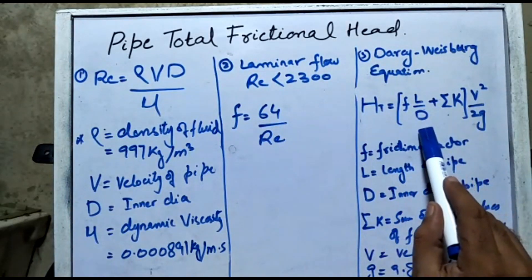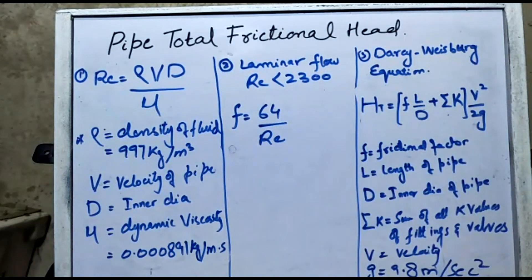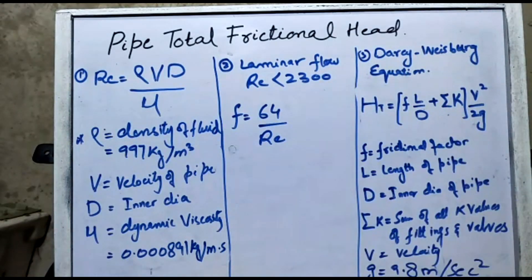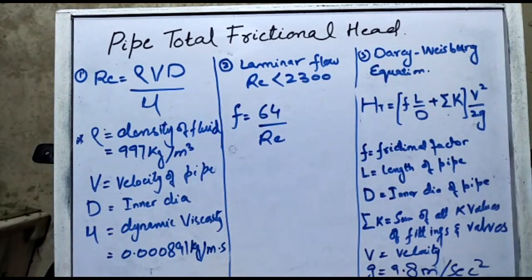...plus the sum of all K-values, multiplied by v²/2g. K-values are manufacturer data regarding the material of the pipe. For example, if we are using galvanized iron pipe, the elbow K-value, tee K-value, and other fitting K-values will be listed in the manufacturer data. v is the velocity of the fluid and g is the acceleration due to gravity, 9.8 m/s².